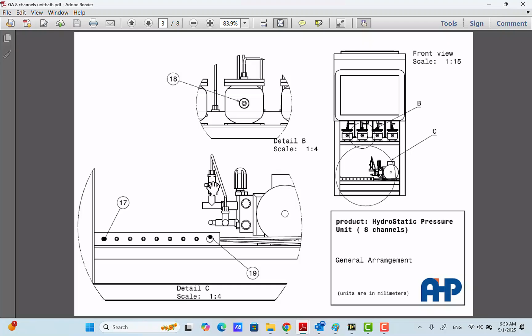Another thing inside the unit, as you see, this is the outlet. This line is the outlet of the pump. And from the outlet, you see a bypass valve connecting the outlet to the inlet of the pump. When the pump is sucking the water to pressurize it, in a sudden start of the pump, there will be a lack of water in the inlet line. That's why, for the fluent working of the pump, there is a bypass line from the outlet of the pump to the inlet of the pump. This delivers a lower amount of water from the outlet to the inlet for the purpose of the fluent working of the pump.